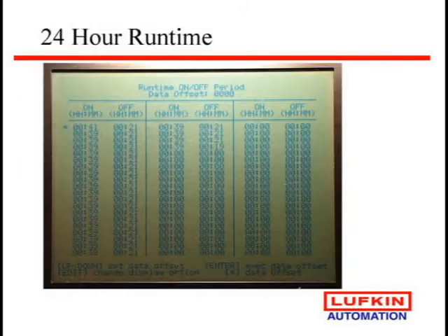All those cycle times are saved in these controllers so you can look at your on/off times. What's important here is the downtime and what we call the minimum pump time. So when a well starts up, you give it a little ignore time to fill. If it's just running on, off, on, off, on, off, something's not right. You've not got it set right. Something's going on, and that should alert you.